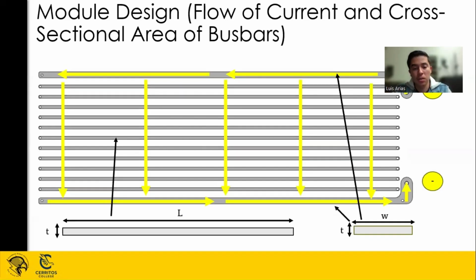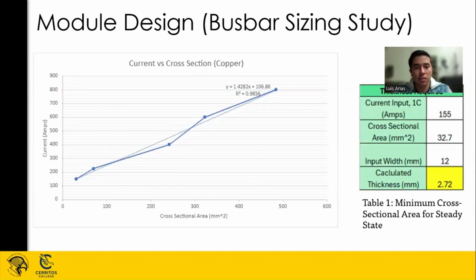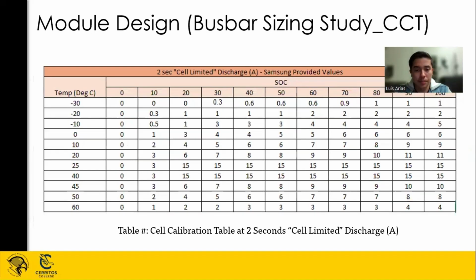It's crucial to know which thickness to use so that it can handle the current and heat. Here we plotted a graph of current over cross-sectional area, given a table by the competition organizers, and used this to calculate the thickness of our bus bars based on our inputted width, at 155 amps, rated for 1C. This represents the thickness for steady state. In our case, with an input width of 12 millimeters, we get a thickness of 2.72 millimeters.